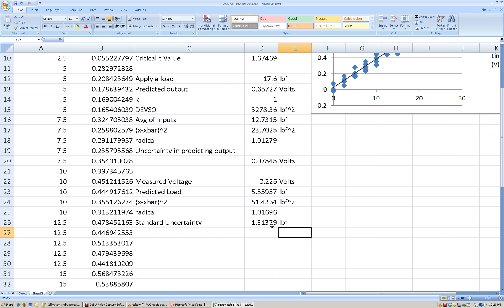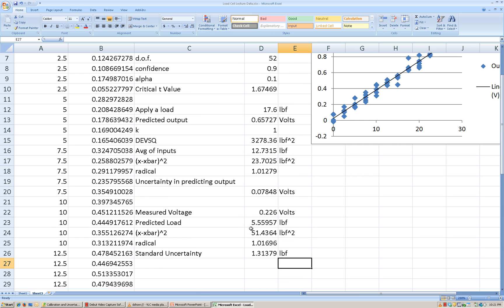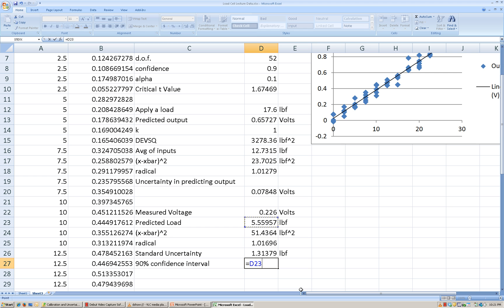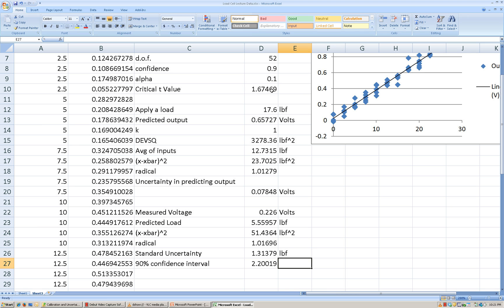This is standard uncertainty — it corresponds to about a 68% confidence interval. If I want to use a 90% confidence interval, I take the standard uncertainty value and multiply it by the critical T value. So the 90% confidence is the standard uncertainty multiplied by the T critical value calculated earlier. With a measured voltage output of 0.226 volts, we can say that the predicted load is about 5.56 pounds-force plus or minus 2.2 pounds-force.